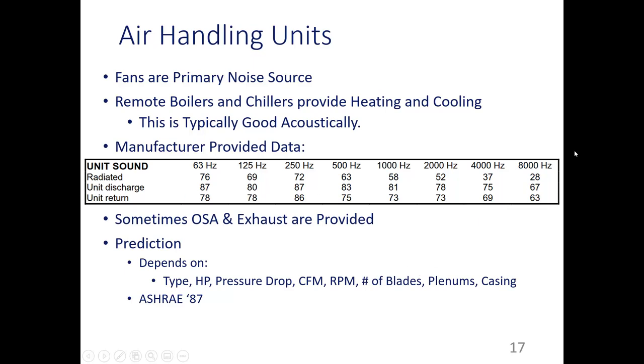So this is pretty common. If it was a packaged rooftop unit, all of this stuff would probably be a little bit higher, because the noise from those condensing units will get into the supply and the return, but it'll be particularly louder on the radiated side. Those condensing units have exhaust fans that, for the most part on a basic unit, are exposed to the environment. There are some where you can get baffles and stuff like that, but they're pretty much just out there in the open. Sometimes there's not even a casing. Sometimes they're just sticking there in a frame, completely exposed to the world. So this stuff out here is going to be a lot higher for a packaged unit, and everything is going to be higher for a packaged unit.